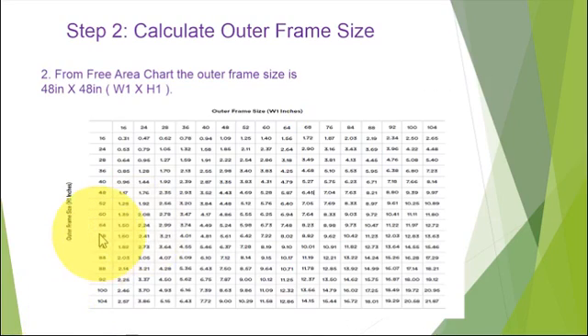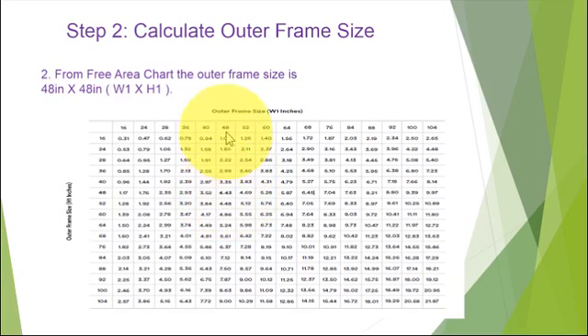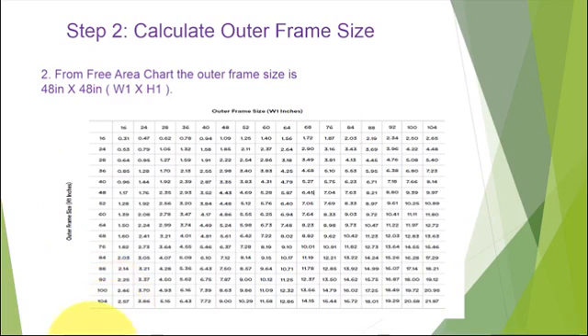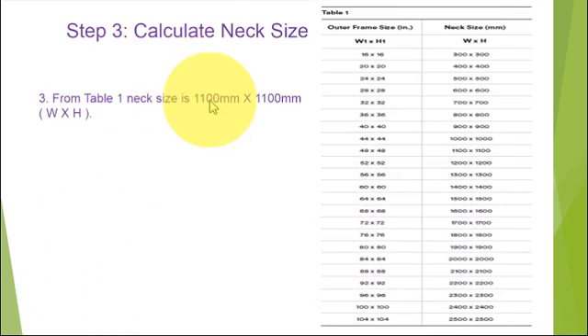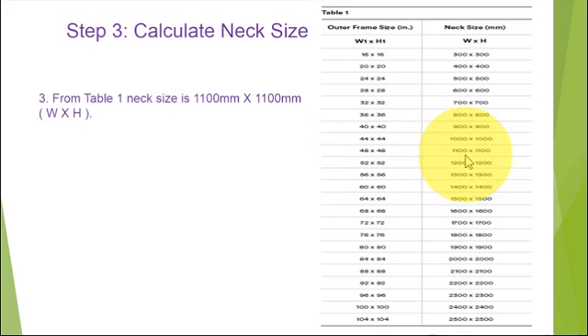We then go to the manufacturer's chart to find the frame size. For example, with a calculated free area of 4.43 square feet, we locate that on the chart and get 48 by 48 inches as the outer frame size. From the next size in the table, 48 by 48 gives 1100 by 1100 mm. By this, we have selected the required size.